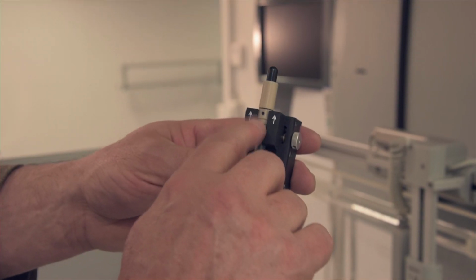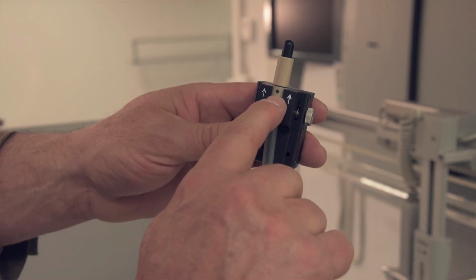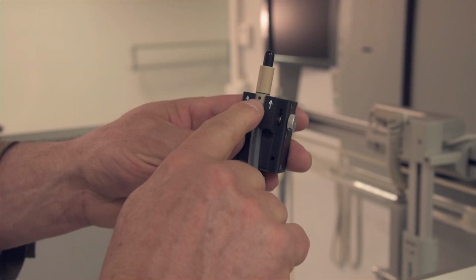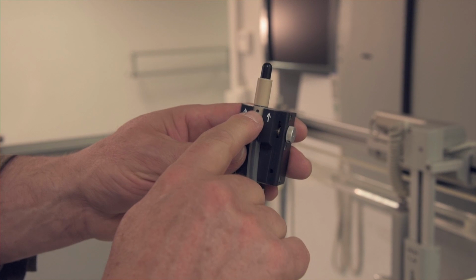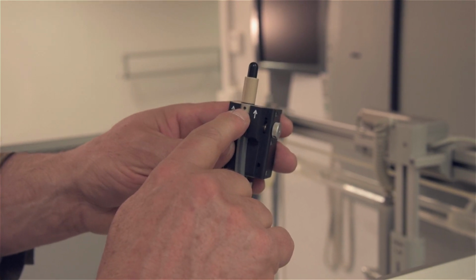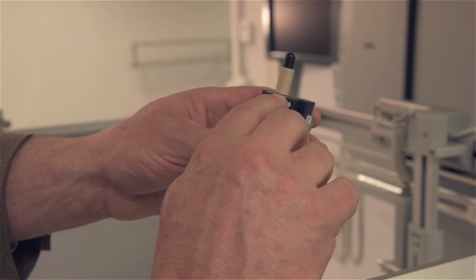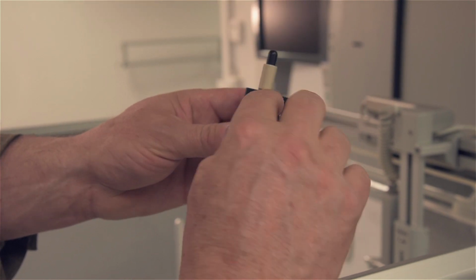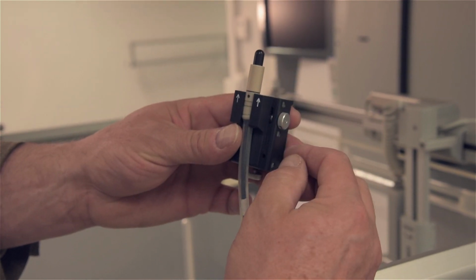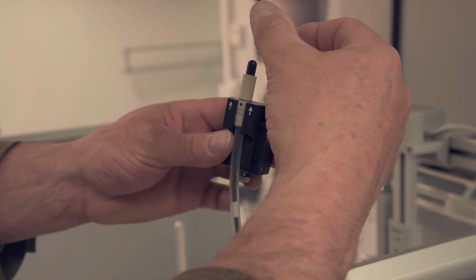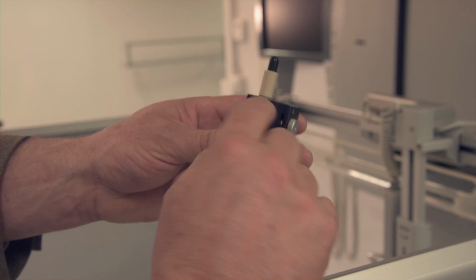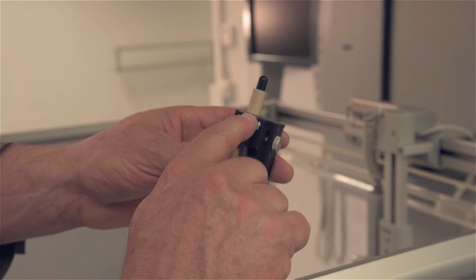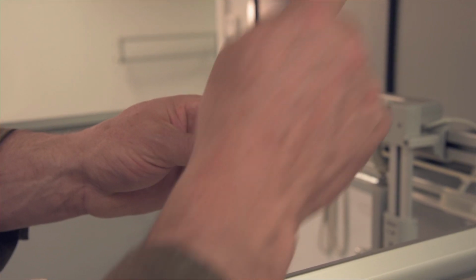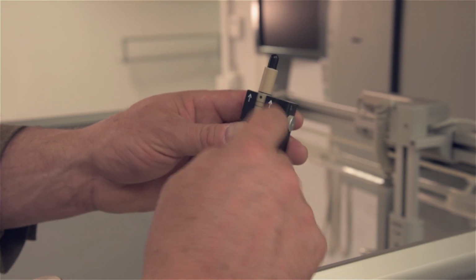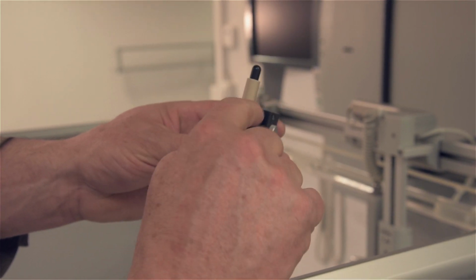I like to set the chamber in the holder such that this dot is facing upward. That's not necessary, but it's a nice landmark, a reference point to use. It's my preference. And this ring slightly beyond the leading edge of the holder. This allows the placement of the alignment cap. If the alignment cap comes to this ring, if the ring is too far back, you won't be able to get the alignment cap all the way on. So you want to make sure that ring is just past this edge.